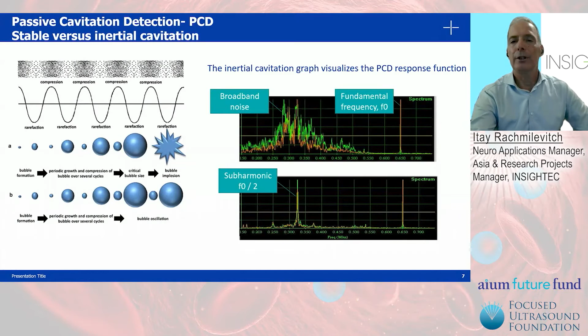Below you can see the graph of the amplitude that is being recorded from the target versus the frequency. You can see the driving frequency, of course, 680 to 650 kilohertz. And we are looking basically at the subharmonic of half frequency, where the cavitation has some signature, in this case, a very tight spike. In the case of the inertial cavitation, the explosion or the inertial cavitation phenomena releases a wide band of frequencies that we can read.